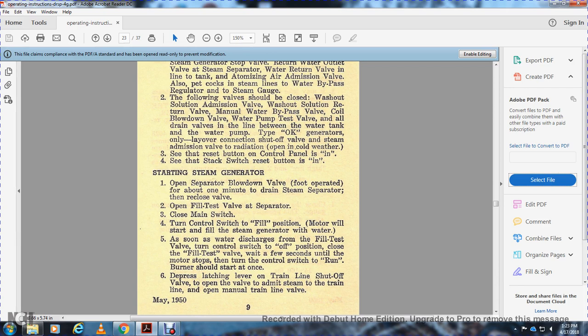Open the fill test valve with the separator closed and the main switch on. Turn the control switch to the fill position. The motor will start and then fill the steam generator with water. 5. As soon as water discharges from the fill test valve, turn the control switch to the off position and close the fill test valve, wait a few seconds until the motor stops.